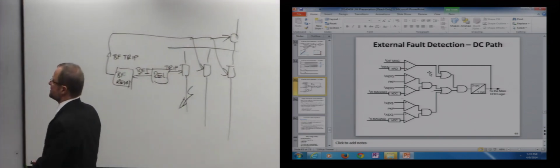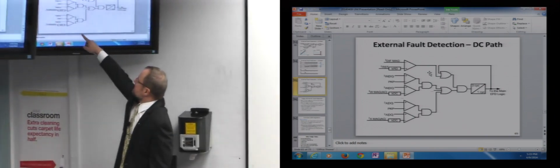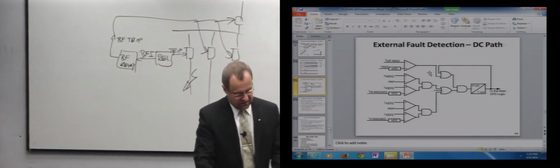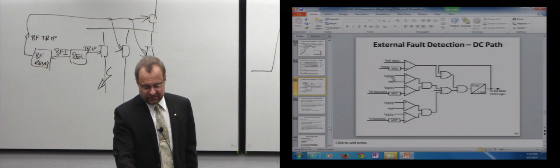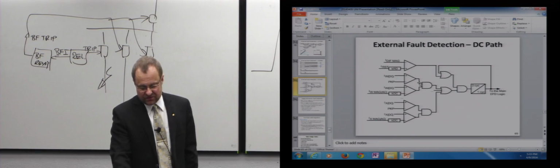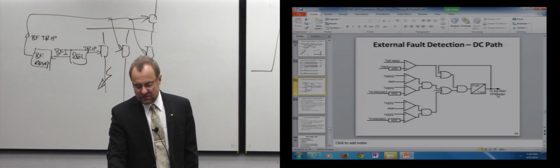So then what is it that I do? I will look at every current and I will say this. If a DC in a given current is greater than a pickup, and DC in a given current is greater than the AC magnitude in it, so I am saying basically DC must be non-zero and it must be significant compared with AC. If both those conditions are satisfied, in any of the currents that I measure for differential protection, and this happens for 3 cycles, I will declare an external fault.